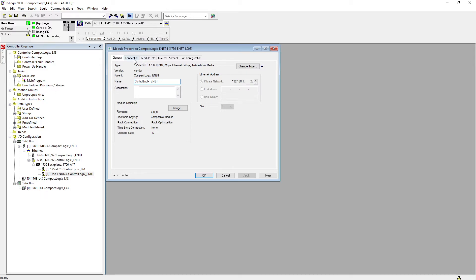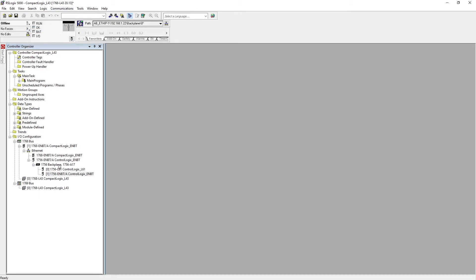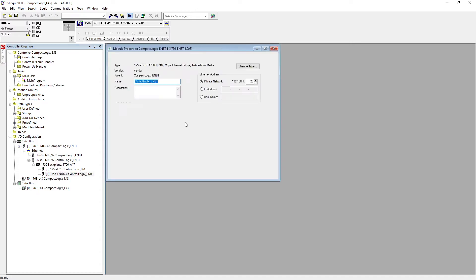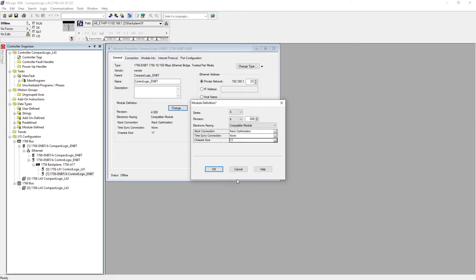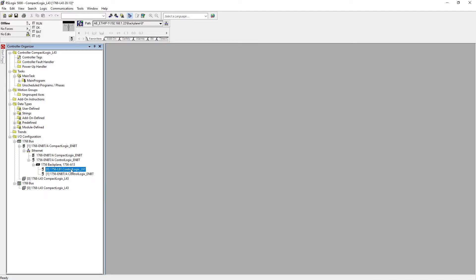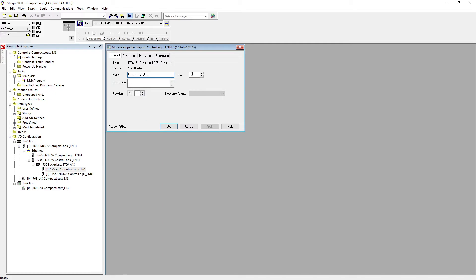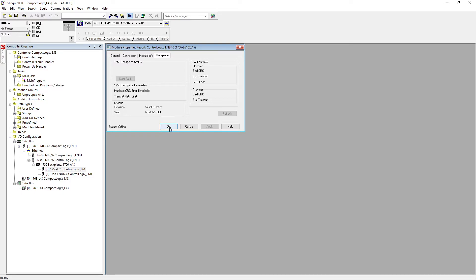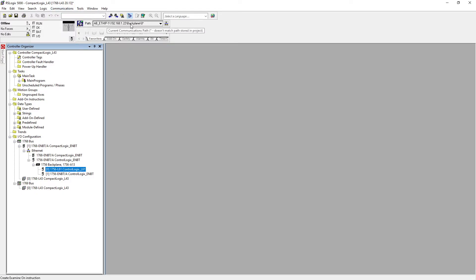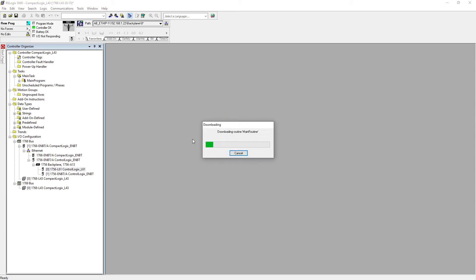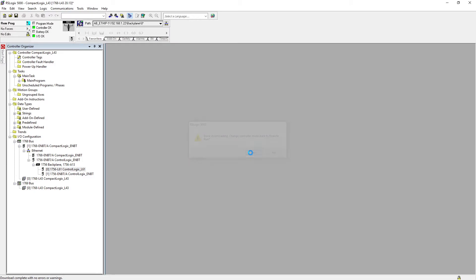That means if you go to the properties side, it should say some kind of error. Slot is 17 — it shouldn't be 17, it is a 13-slot chassis. So what we're going to do now is go offline, change that to a 13-slot chassis, hit yes, OK. Looks OK — the path is already selected over here so we're just going to go straight to download. Let's see if any error will occur. No error. So you see, if you select the wrong chassis or wrong slot that will be an issue.